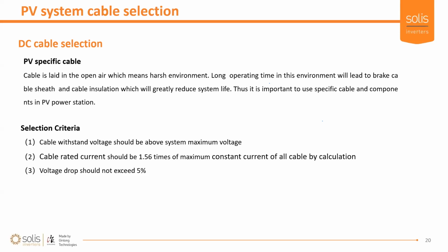However, there's a little bit of an interesting point here. Even if you have 100 volts DC on the PV, you would think you just need to rate the cable for 100 DC, but generally your surroundings are earthed, and that could be running at 240 volts AC. I'm guessing, I need to think about that one a little bit, but about 200 volts AC running on that earth relative to your DC conductors, and therefore you would need to have your insulation at least able to handle that.